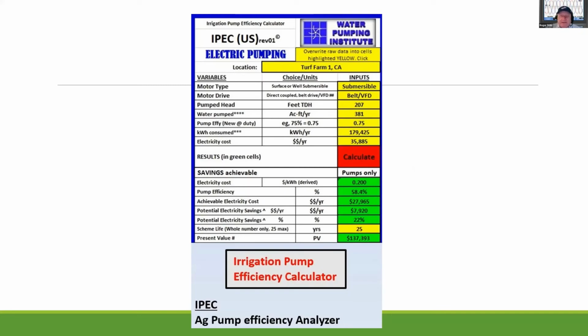It gives a very nice overview, and you can actually download this to your iPhone and put in some of these parameters, like what your pump head is. This is before anybody does anything. Find out if you have just a belt drive or whatever it is, and you can put in a VFD or not. You can find out whether it's a submersible pump, because a submersible is on average about 10 to 12% less efficient in the amount of kilowatts it uses per total horsepower. So you have a loss there.